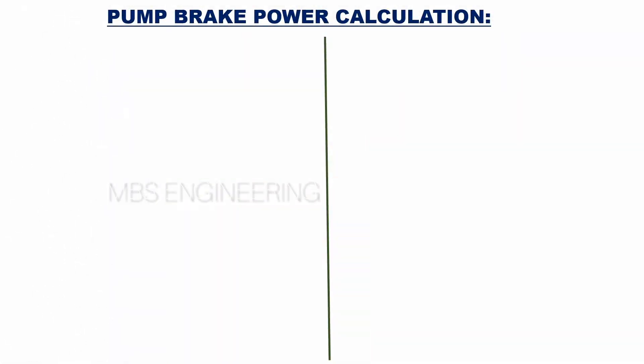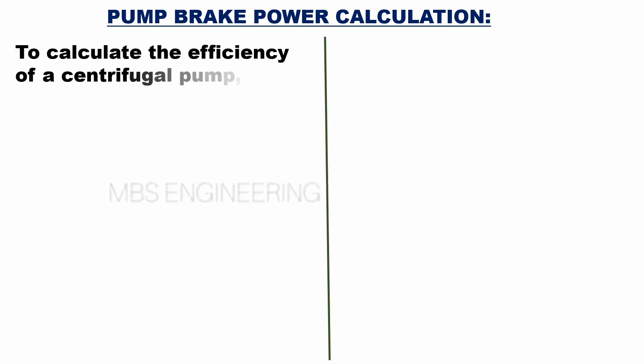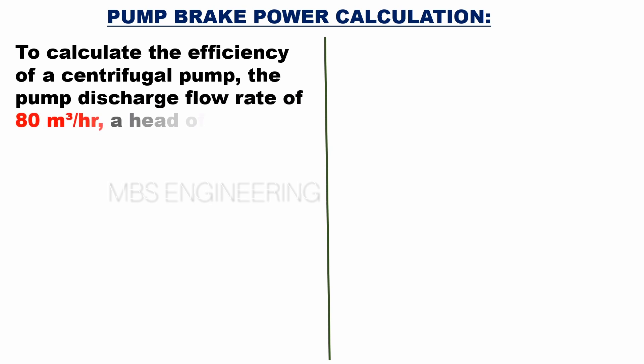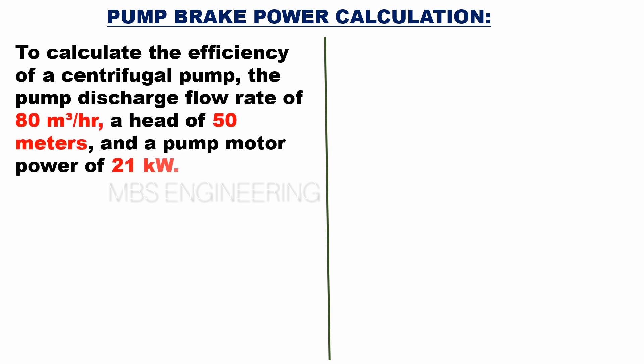We will now calculate the pump brake power for a centrifugal pump using the following sample example. To calculate the efficiency of a centrifugal pump: the pump discharge flow rate is 80 cubic meters per hour, a head of 50 meters, and a pump motor power of 21 kilowatts.